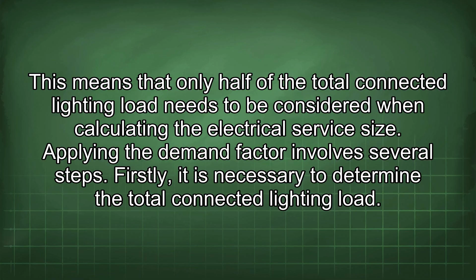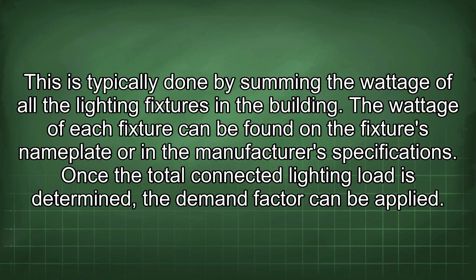Firstly, it is necessary to determine the total connected lighting load. This is typically done by summing the wattage of all the lighting fixtures in the building. The wattage of each fixture can be found on the fixture's nameplate or in the manufacturer's specifications. Once the total connected lighting load is determined, the demand factor can be applied. In the case of a place of worship, the demand factor is 50%, so the calculated lighting load is simply half of the total connected lighting load. For example, if a church has a total connected lighting load of 20 kVA, the calculated lighting load for service sizing purposes would be 10 kVA after applying the 50% demand factor.